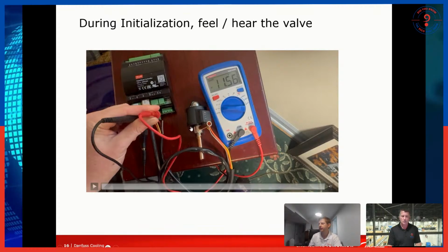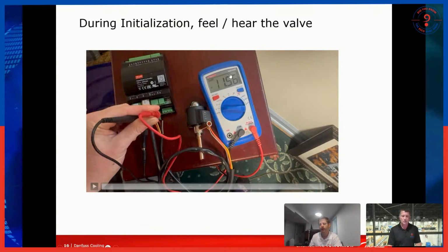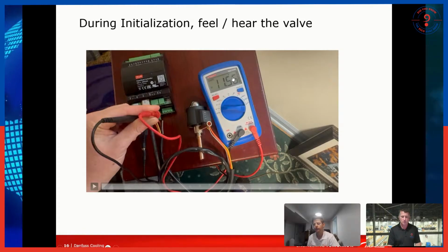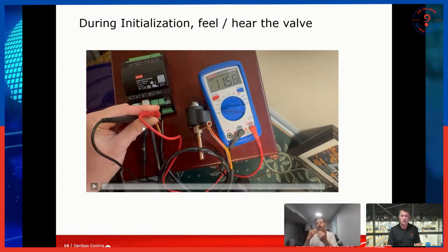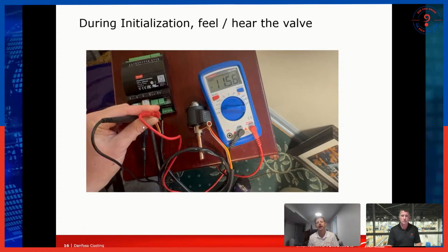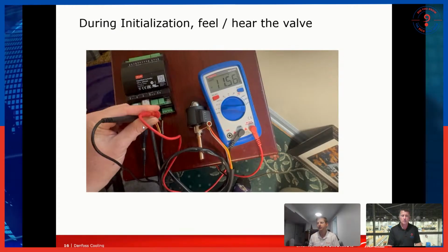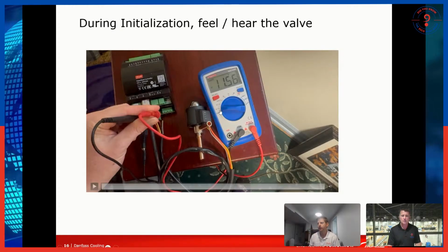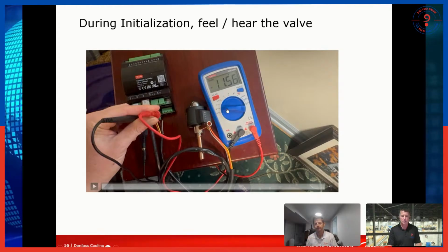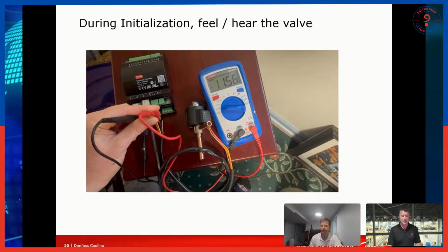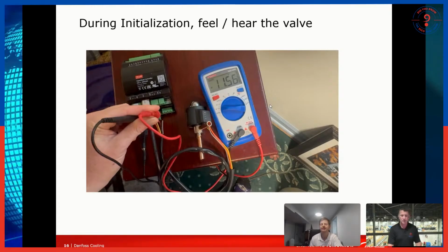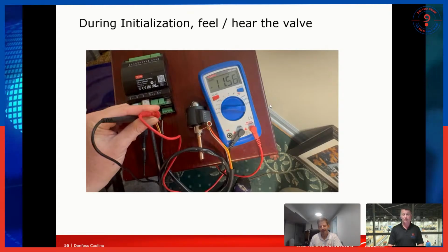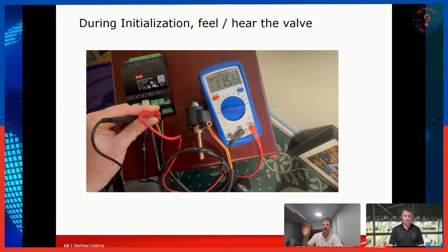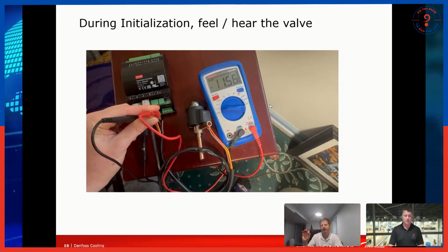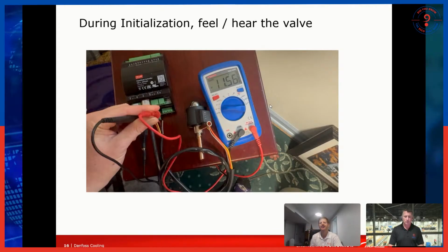And you can see here too, I've got the voltmeter up on it, and it's measuring 12 volts. These controllers do send out pulses of 12 volt DC power, but because it's doing it so many times a second, you have to set your meter to AC to actually be able to see it. But it is a DC voltage that is being supplied from the control. Yeah, the controller is providing DC power, but it's doing it really quickly.